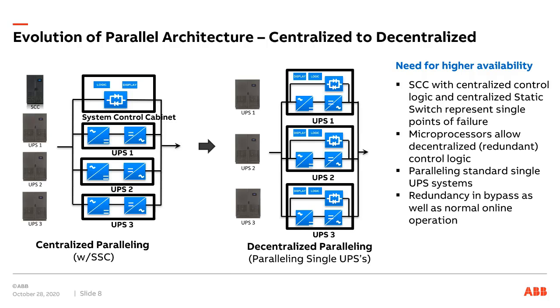And again, I'm showing three, but this could be 4, 5, or 6 in parallel. It's essentially paralleling single UPSs, and they operate the same way, except that each UPS is now a complete UPS. It has its own static switch, its own control logic, its own display, and so on and so forth. And because of the more powerful microprocessor control, each UPS in this lineup can control the operation of the total system.